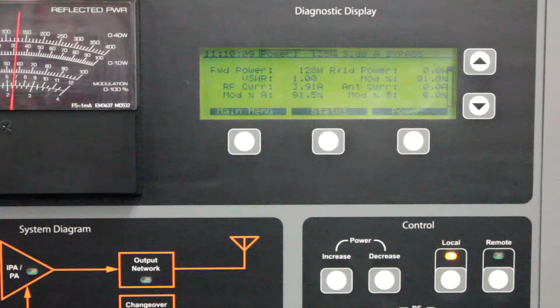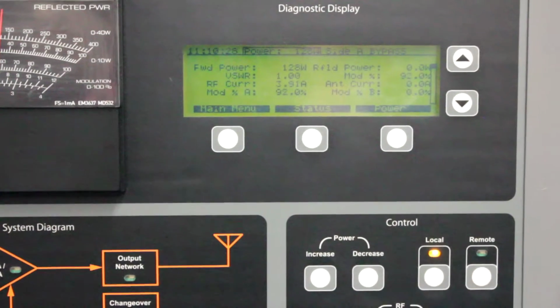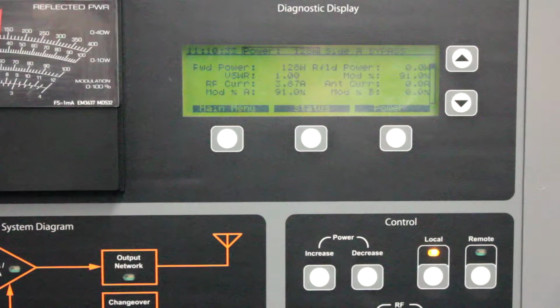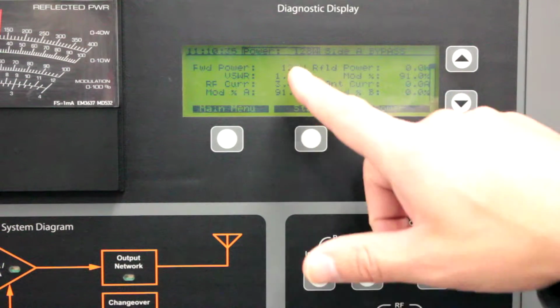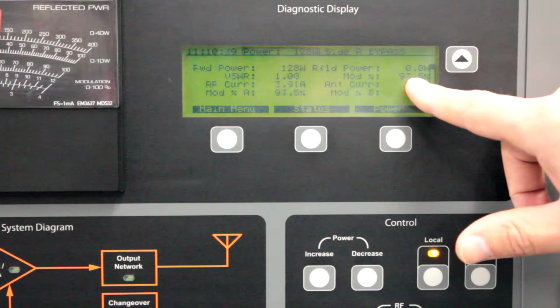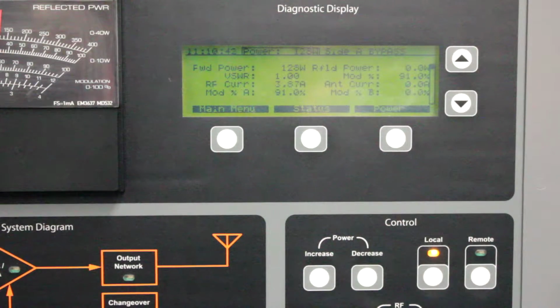I'm a member of Nautel's customer service team, and I'm going to show you how to properly compute the thresholds for the Vector series transmitter. In this example, we're using a Vector LP 250 watt system connected into a test load. I currently have it set up for its operating levels. It's set to a forward power of 128 watts and a modulation percent of around 90 to 95% modulation.